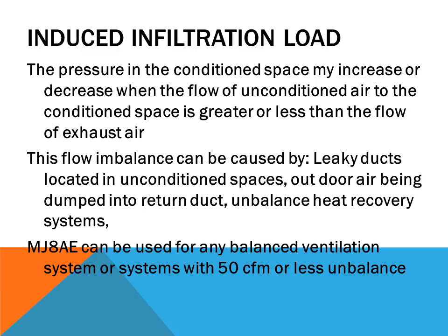So induced infiltration loads are the things that we look at. In the Manual J, we talk about infiltration. Infiltration is air that is coming from outside to inside of the structure. A lot of times it's from things like leaky ducts, as I was mentioning earlier. If they're not sealed, and not using mastics to close up any joints, we can pull air into the house if it's in non-conditioned space, such as a crawl space where the humidity can be pretty high sometimes. Because of that, we bring in air that is laden with moisture.